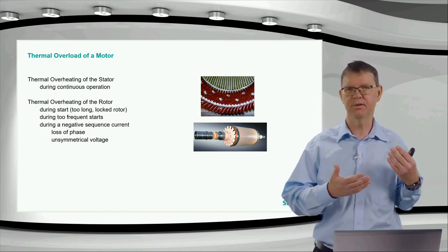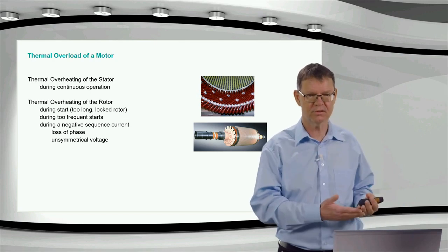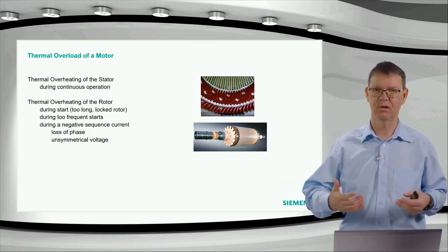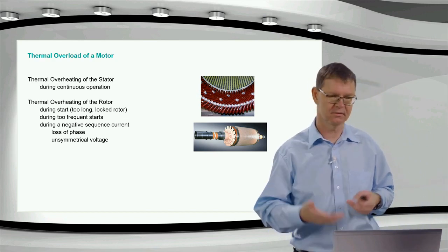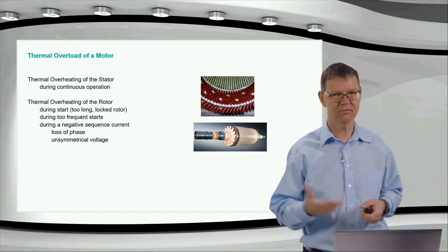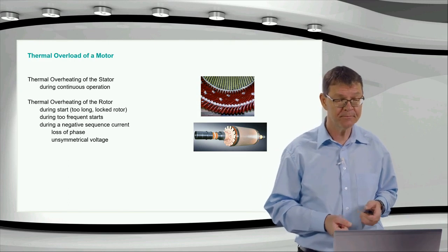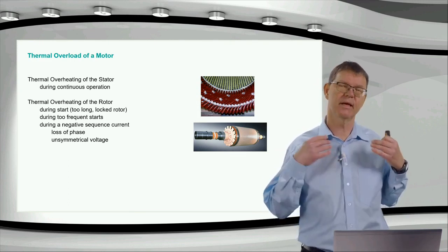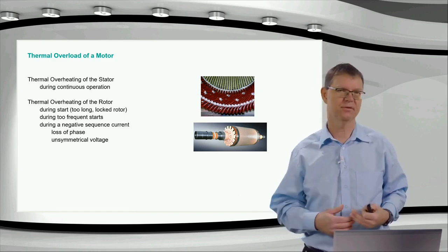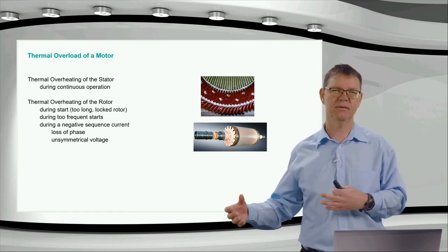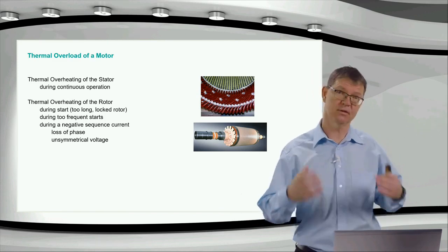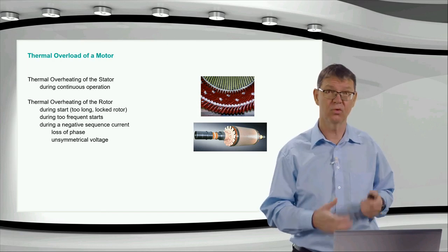So there can be the problem that I have a too long start, or even the rotor does not rotate at all when it is locked, because of the machine or whatever the process behind is. And I can have too frequent starts. I cannot start one after the other; I need to have some time in between the starts of the rotor. If I do this too often, then I also overheat the rotor.